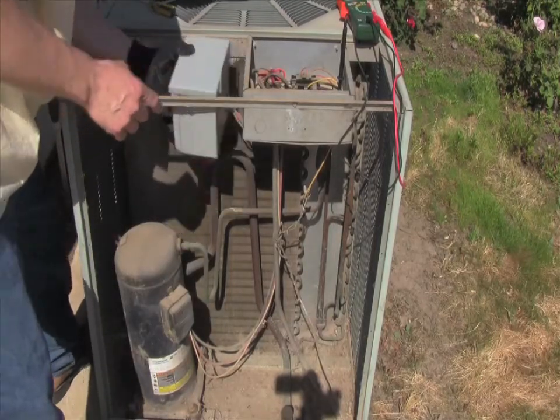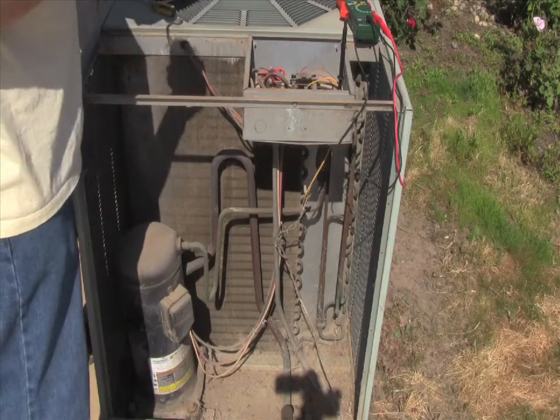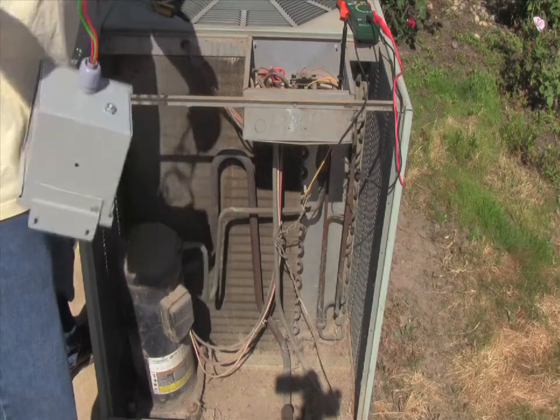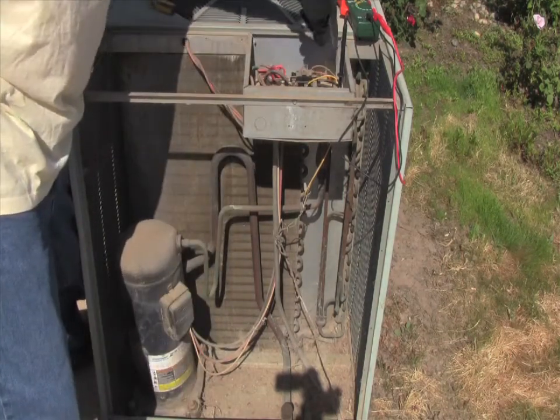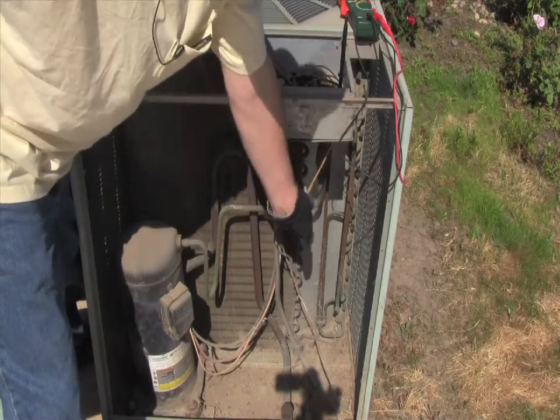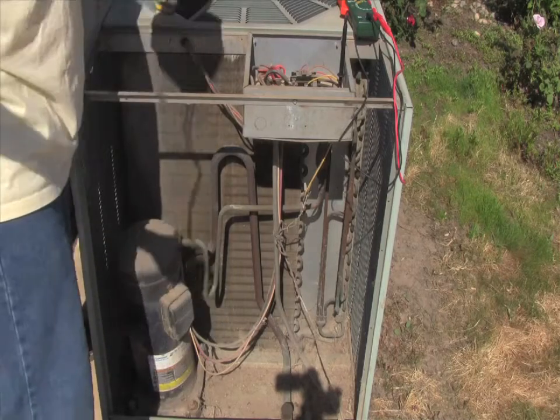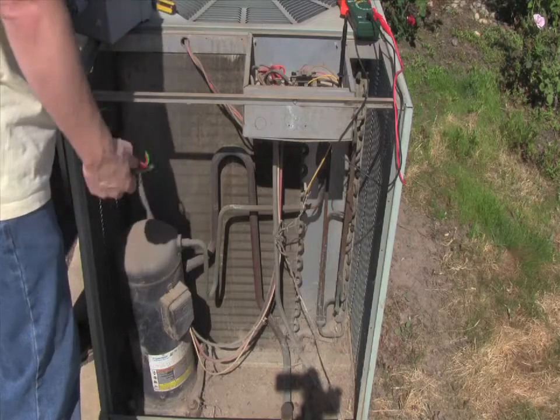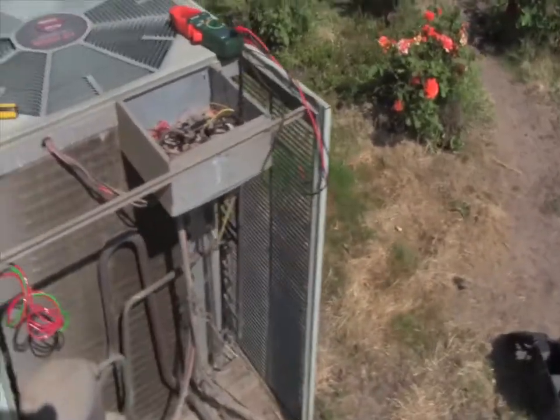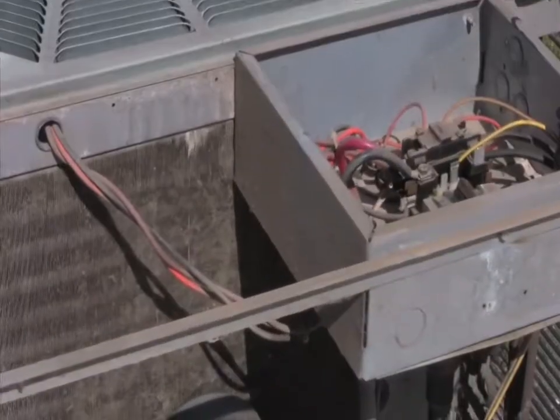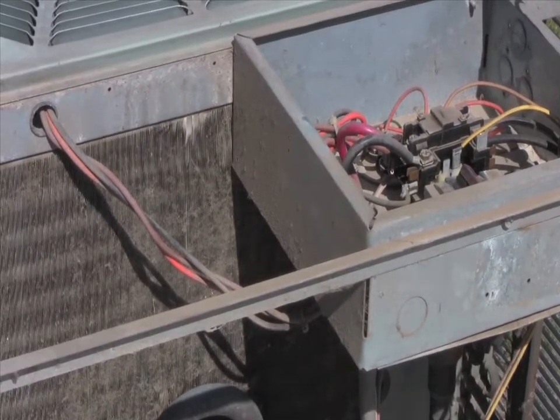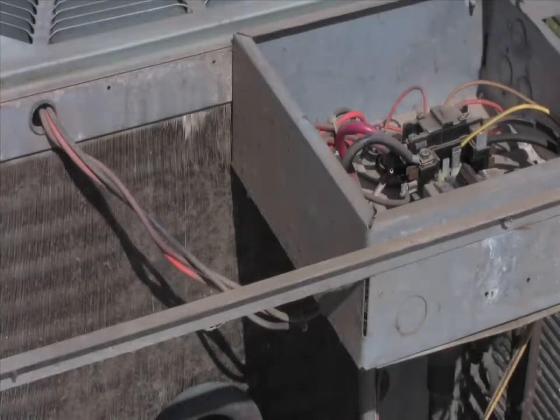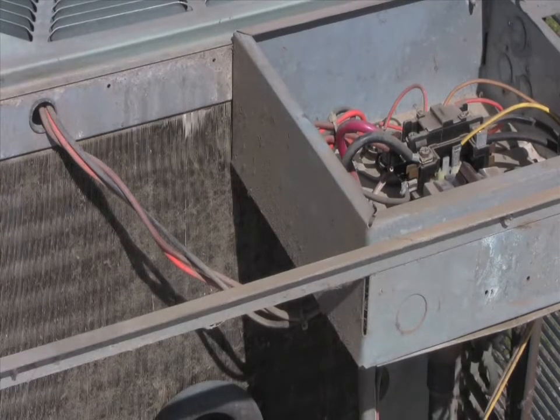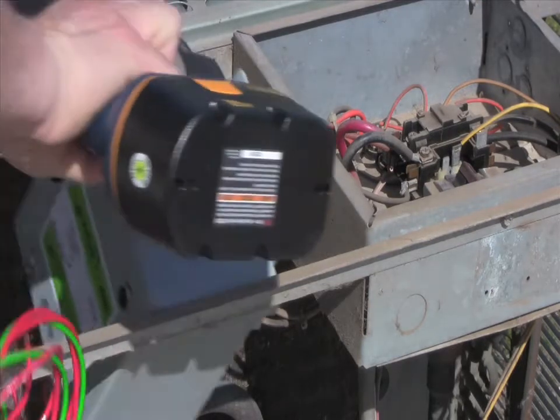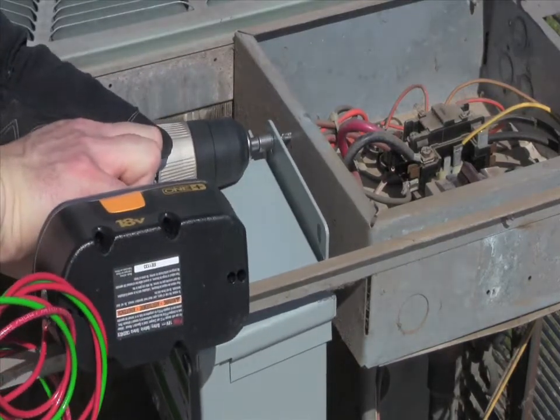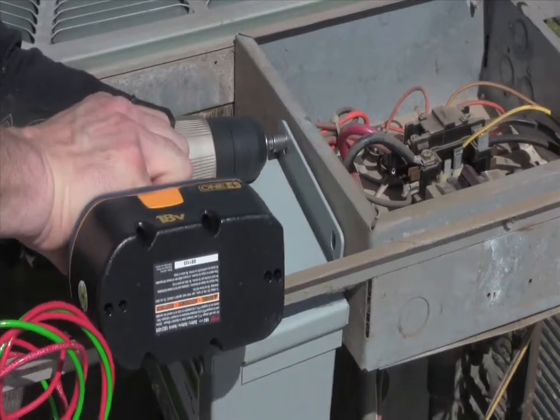But you have to make sure that you run the wires into the control section through the high voltage knockout. You cannot use the low voltage knockout. The low voltage knockout is over to the side, over here. Nothing goes through that knockout except for low voltage. You got to keep them separated. So we found a suitable mounting location over here on the side, right there. And there happens to be a hole already made, so let me get a screw. These are self-tapping sheet metal screws. I'm going to set that right there, get that going. And always look on the other side, make sure you're not going to drill into something you don't want to drill into.